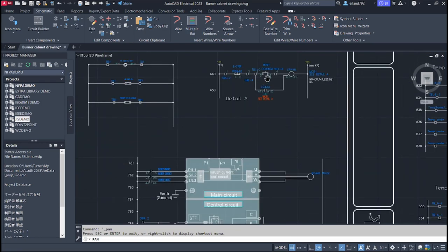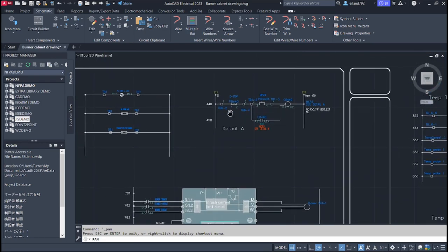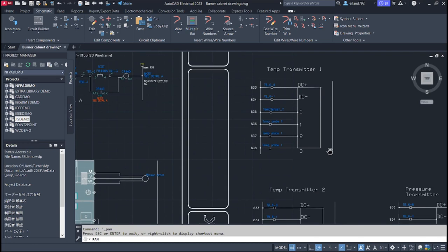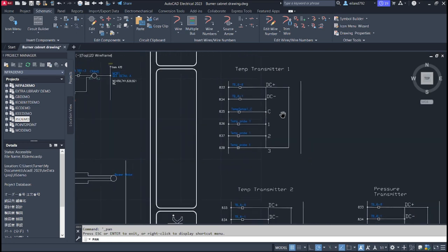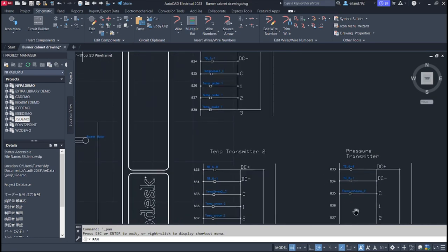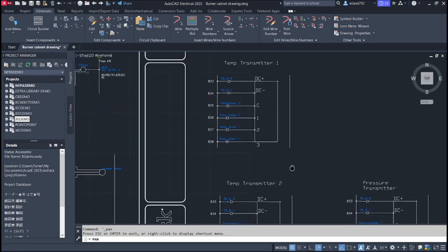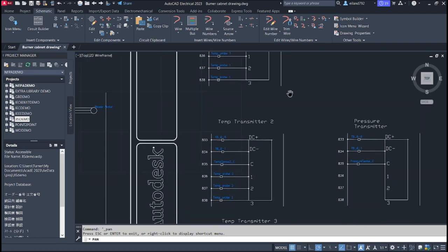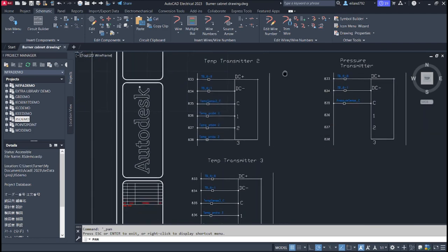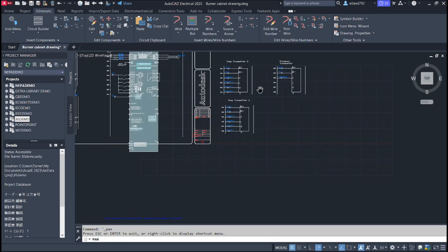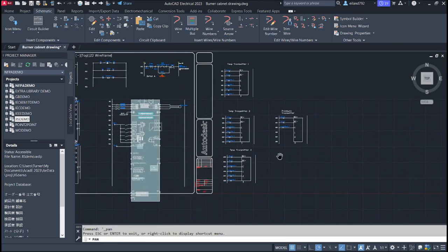Here's my e-stop circuit. I have an e-stop, a reset, this control relay, and a holding contact. And then my different transmitters, they're all the same wiring, except the pressure sensor doesn't have a temp probe it's going out to, but here's my 3 temp sensors and then the pressure transmitter. So now I'm gonna go back in the cabinet and show all these components and where they are in my cabinet. So let's go do that.